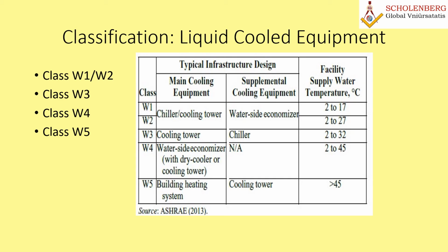And class W5. In these data centers, the temperature of water exiting the IT equipment is high enough to reuse to heat local buildings, thereby increasing the energy efficiency, reducing the capital expenses with chiller-free operations, and making use of waste energy. This is for the use of class W5, that is liquid cooled equipment.